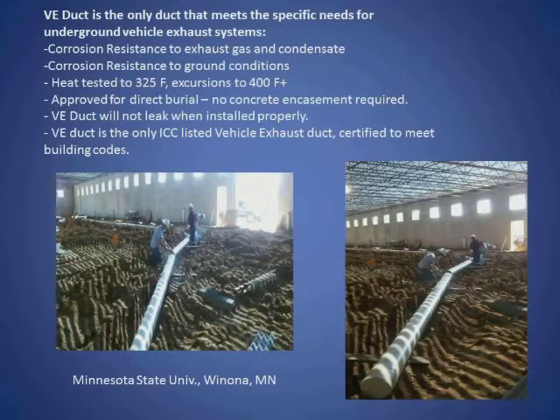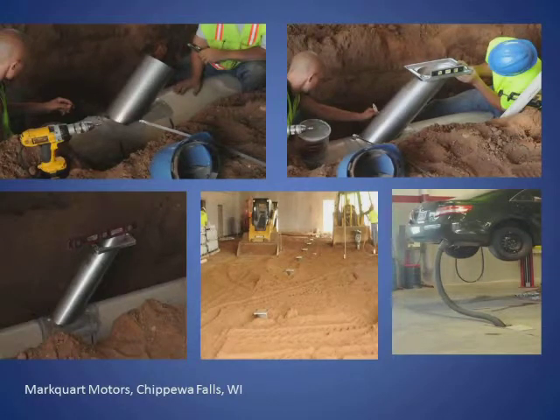The photos we're looking at show Minnesota State University at Winona. This is an auto tech room that's going in at the university. And there you see the long sections being joined that will then be put in the floor. Here we're looking at an installation at Markquart Motors in Chippewa Falls, Wisconsin. What you see are the workers putting Monoxivent stainless steel pieces with the saddle on the duct. They're using duct seal and stainless straps, and they position them all. If you look at the center photo, you'll see they've now compacted all the sand and they're ready to pour. The next photo on the right shows the finished product. The hoses in this system, the hose is stored in the duct itself.